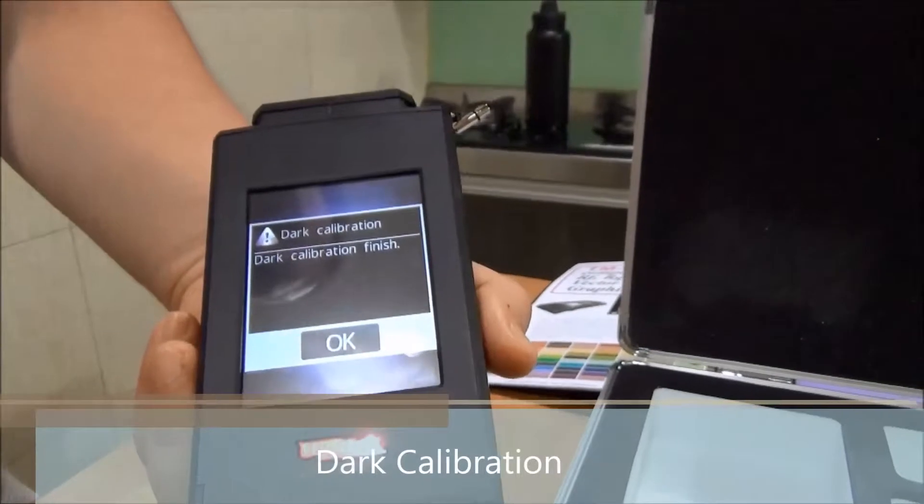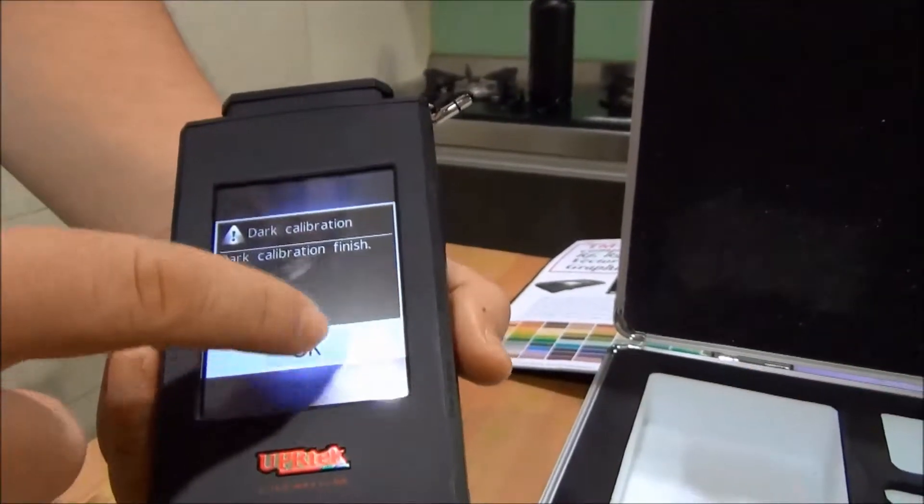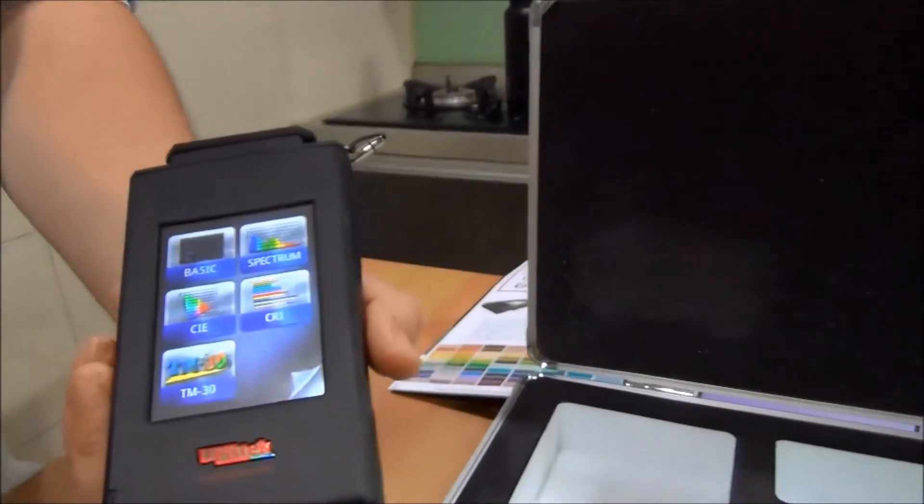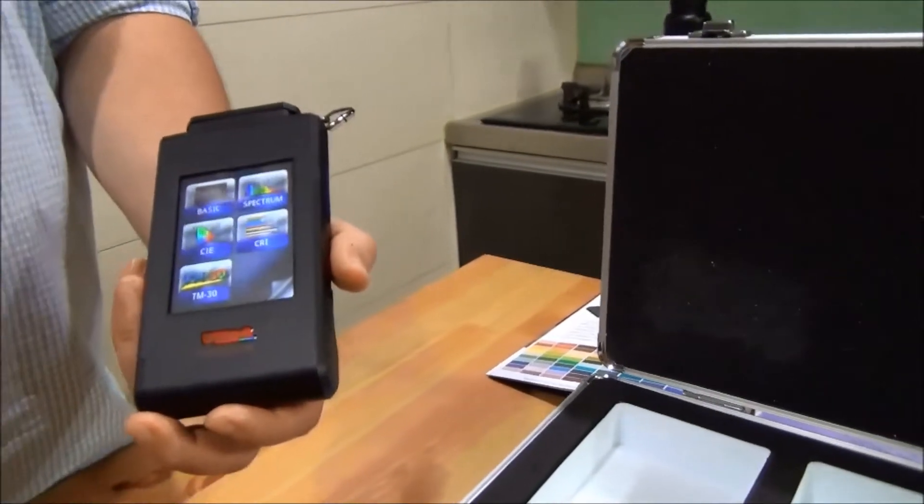And then you need to have the cover sensor on when you do this calibration. Click OK. Takes a couple seconds, start calibration, it has finished. And we recommend for you to do this every time you turn it on to make sure you get the most out of your device.